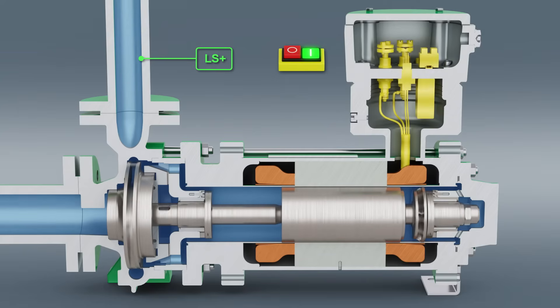The partial current is diverted at the impeller into the high pressure area and used to cool the motor and lubricate the hydrodynamic slide bearings. This partial flow runs through the hollow bore shaft at the end of the motor and back to the pressure side.